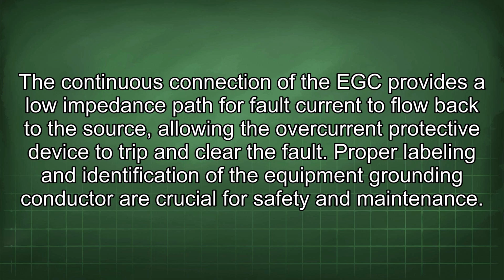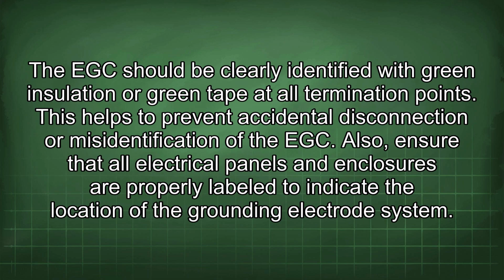Proper labeling and identification of the equipment grounding conductor are crucial for safety and maintenance. The EGC should be clearly identified with green insulation or green tape at all termination points. This helps to prevent accidental disconnection or misidentification of the EGC. Also, ensure that all electrical panels and enclosures are properly labeled to indicate the location of the grounding electrode system.